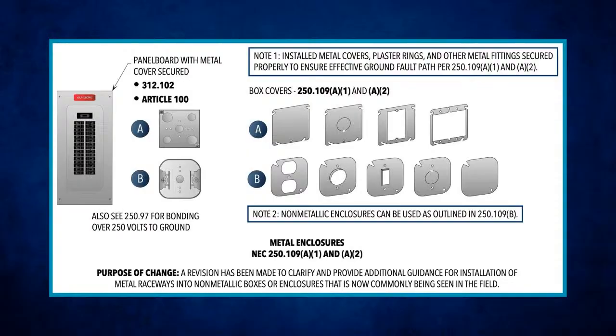100%, let's go. This is where you get into your equipment grounding and equipment grounding conductors. They made some changes here for further clarification dealing with metal and non-metallic enclosures. With metal enclosures, they gave two rules you have to comply with: if you have metal enclosures, they're required to be used to connect bonding jumpers or your equipment bonding jumpers, or both. The reason you do that is to connect them together to become part of the effective ground fault current path.